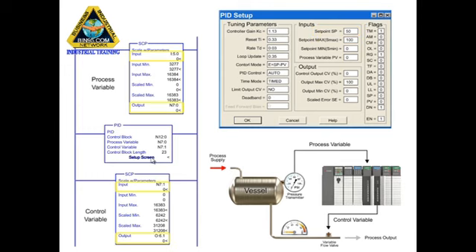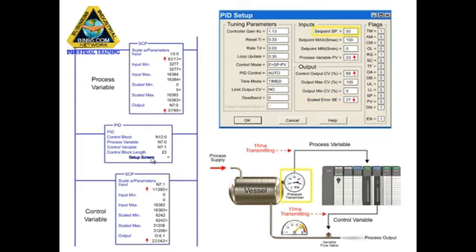As the PID instruction is executed, a scaled error is generated by subtracting the process variable from the setpoint. By increasing the control output, the error is reduced to attain the setpoint as the PSI is raised in the system. In other words, the valve position is gradually closed to reduce the pressure loss. Upon reaching the setpoint in the system, the control output and scaled error is reduced to zero.